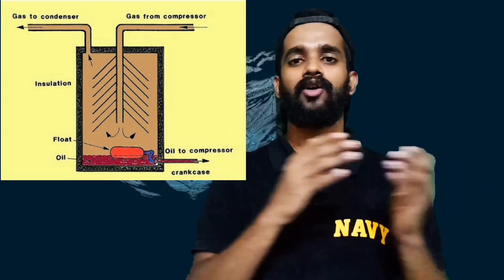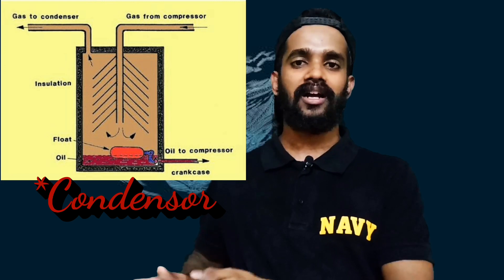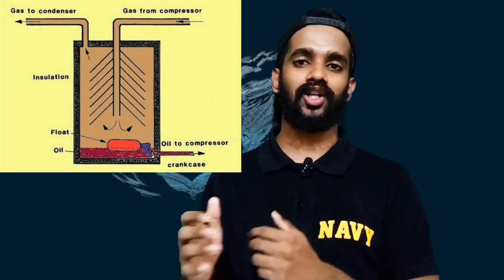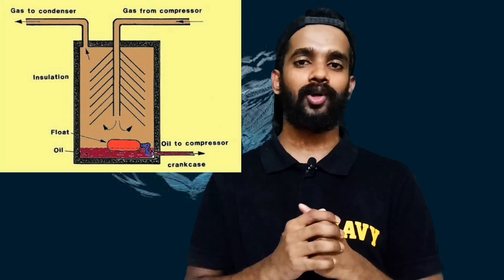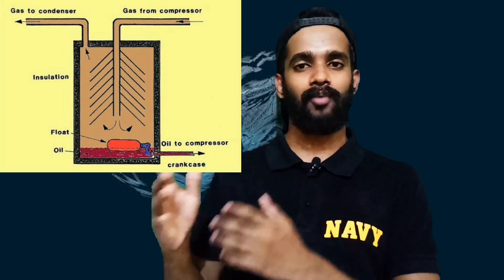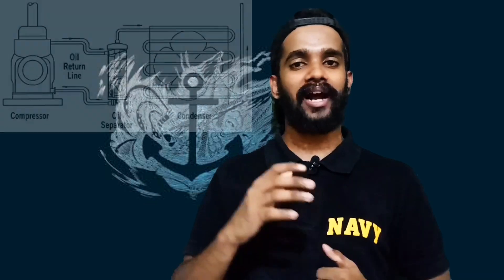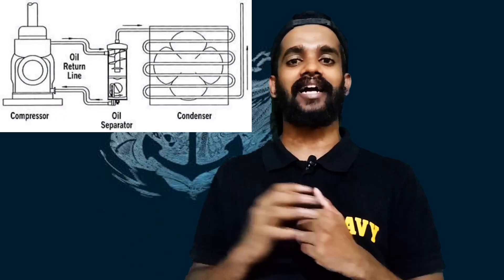Via the discharge side, the refrigerant goes to the condenser and the receiver present in the marine refrigeration cycle. The typical construction of the oil separator is very interesting because it is well insulated from the atmosphere — you don't want heat to be rejected to the atmosphere, and you don't want the refrigerant condensing at that point. You want the refrigerant to be condensing in the condenser, not in the oil separator.